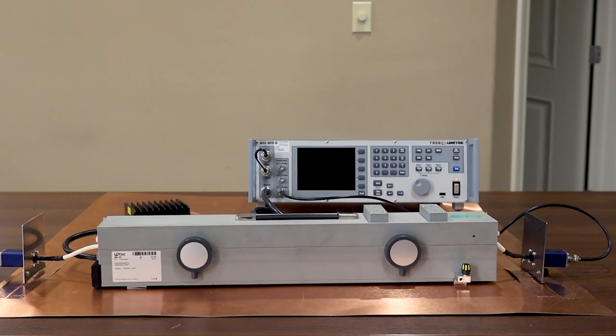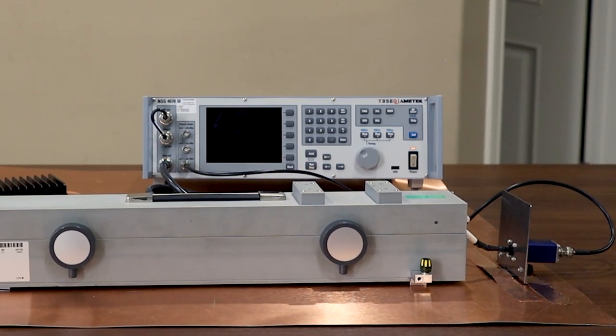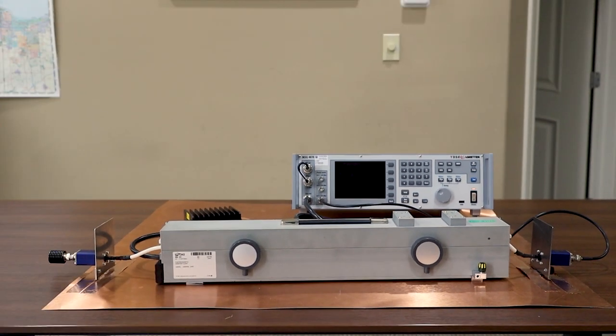Taking a look at our 4070 now, we have the amplifier output going to our 6 dB attenuator and then on the backside to the input on our clamp. Finally, all the way on the right side of the unit, we have our power meter connected to the other side of the clamp which is not terminated. Now let's take a look at the display on our Teseq NSG 4070 and run the test level calibration.